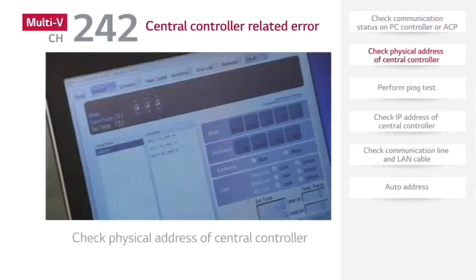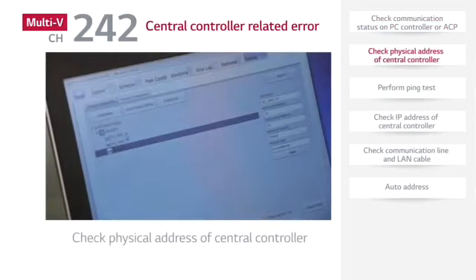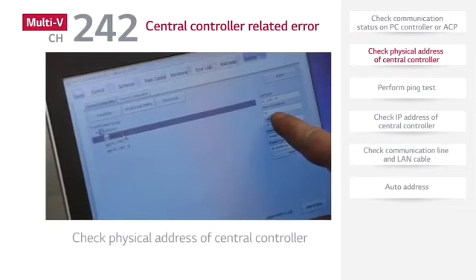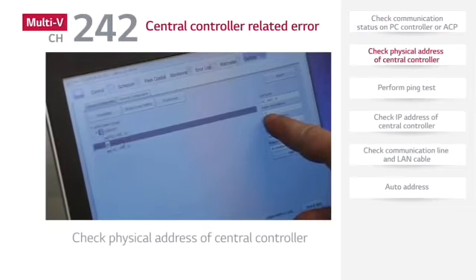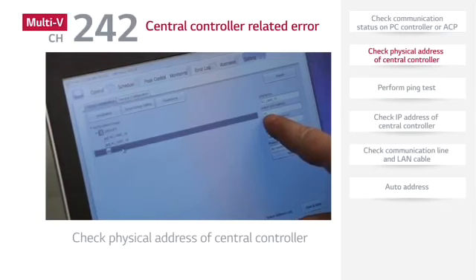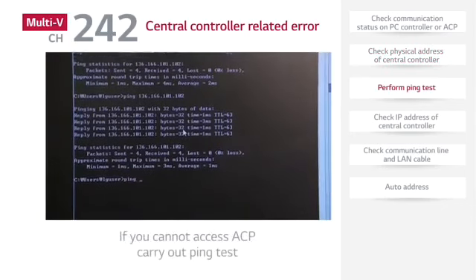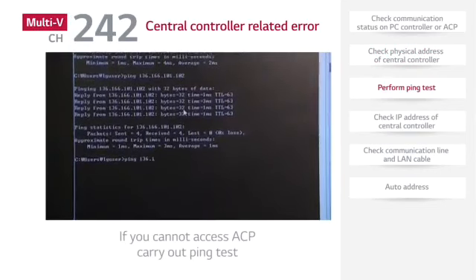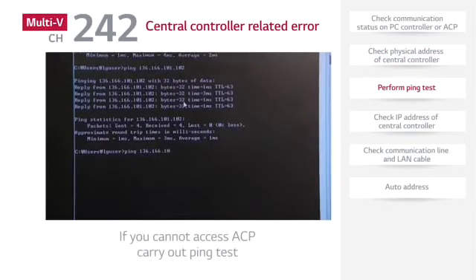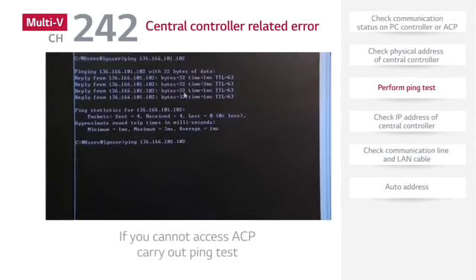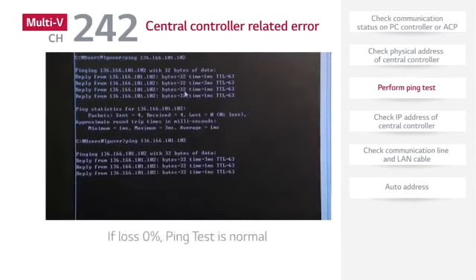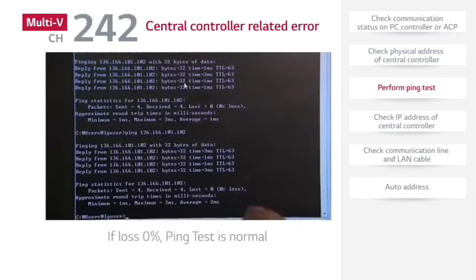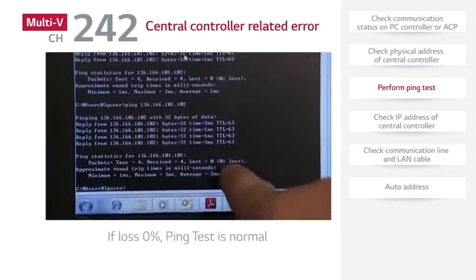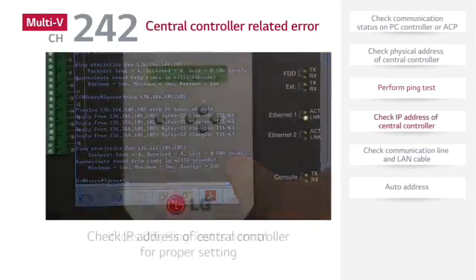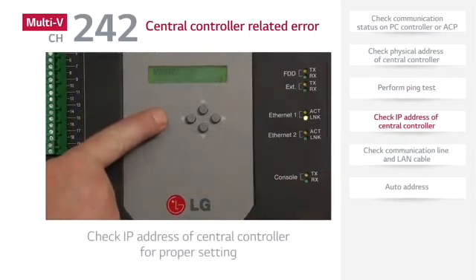Check the target of error CH242 on the screen, and check the physical address of central controller and physical address of the indoor units. At this point, if you cannot access ACP, you have to carry out a ping test. Next, check the IP address of the central controller for proper setting.